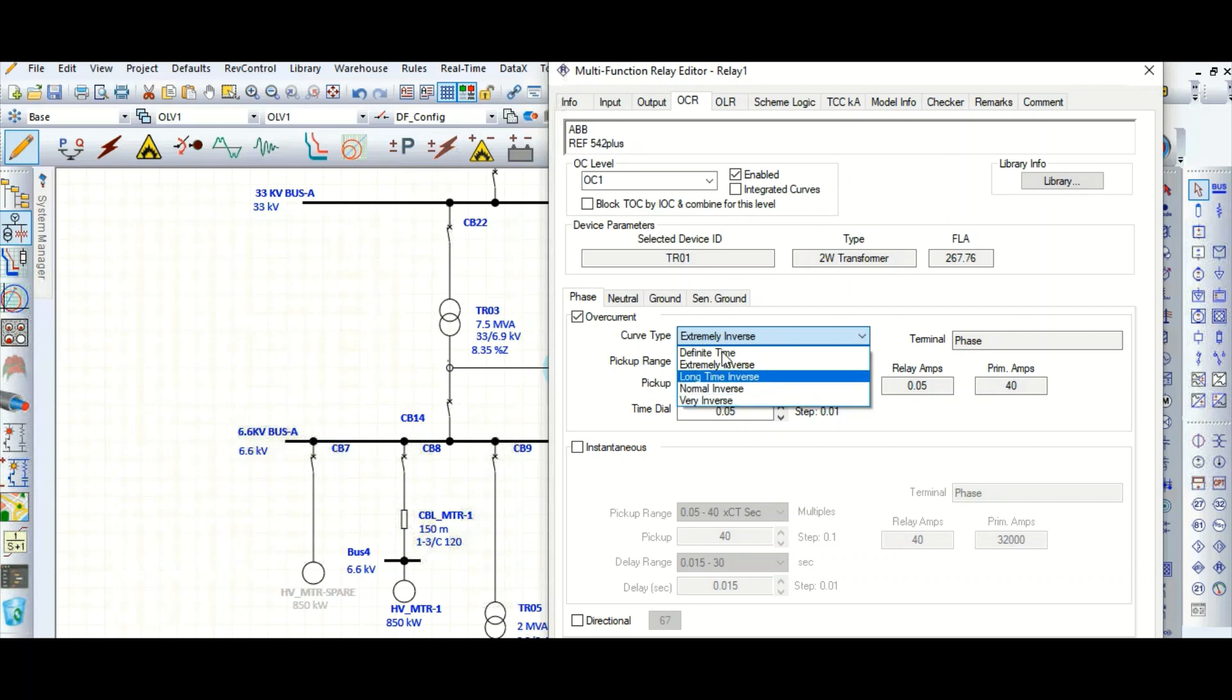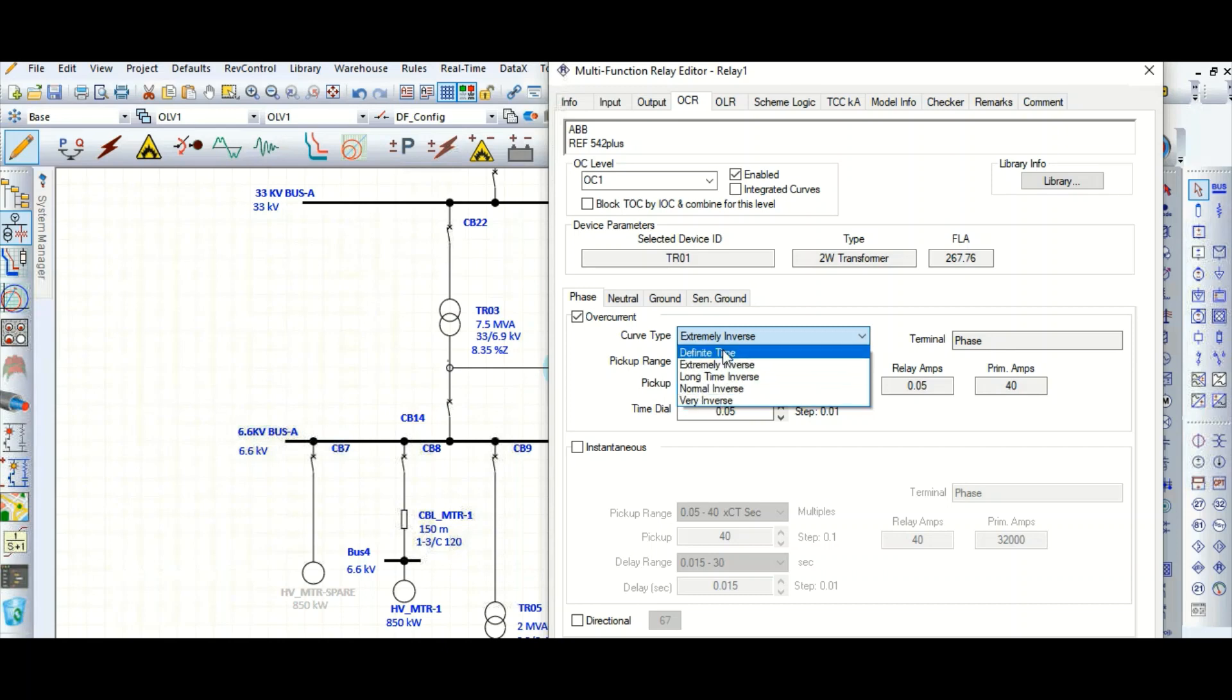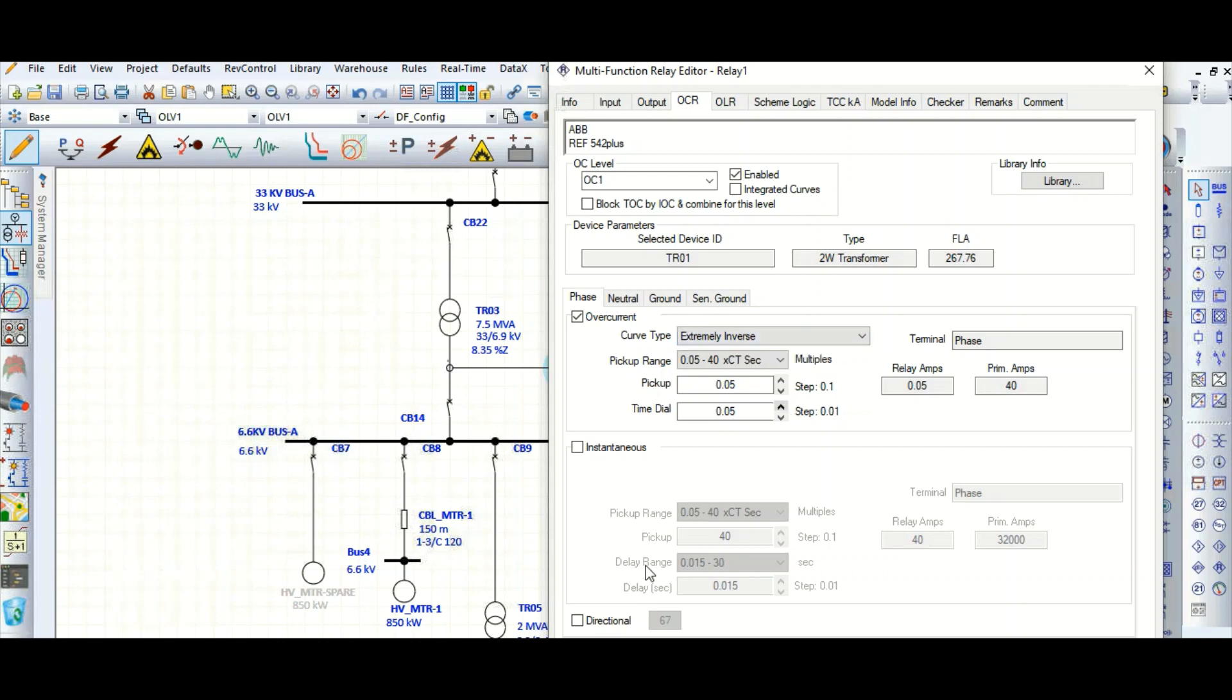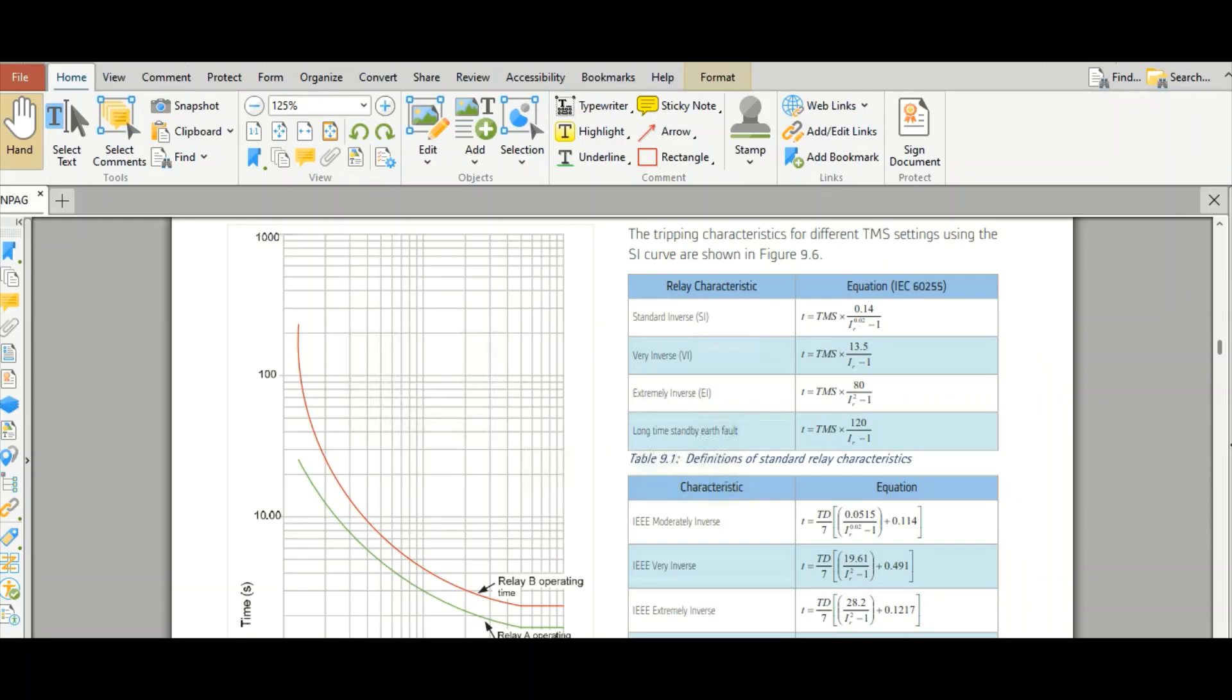Let's select this whether this is definite time, extremely inverse, long inverse, or normal inverse, or very inverse. So these are the relay types. So if you are not familiar with this IEC relay curve, I will show you one manual. Okay, that's fine. Here you can see this is standard inverse, that means normal inverse, and this is the equation from IEC 60255. What will be the time multiplier?